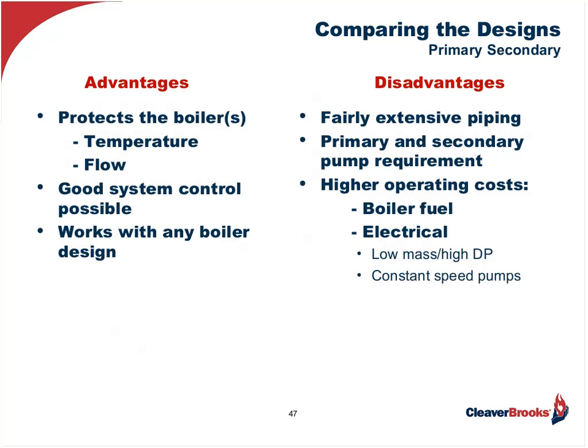Now, just summarizing here, what are the advantages and disadvantages? Well, primary, secondary will protect the boilers. You have that minimum flow in there, so they're not going to get hot spots. They're not going to cycle too much, ideally, if you have buffer systems. They can provide pretty good control, and it will work with any boiler design. However, you have to have more extensive piping, more equipment, and as we've shown with the examples, it's going to be a much higher operating cost.